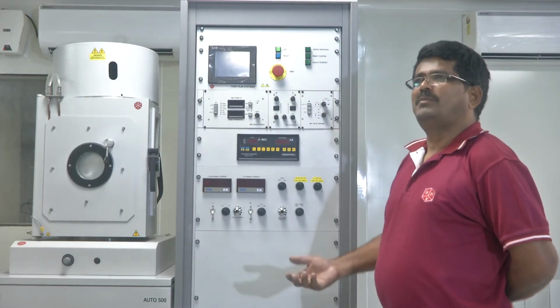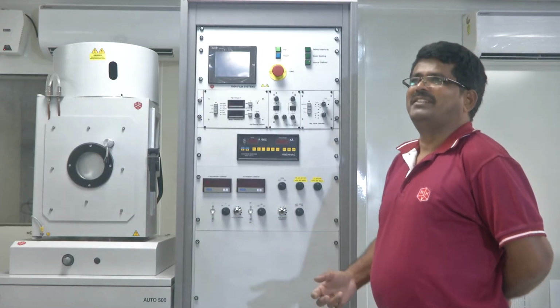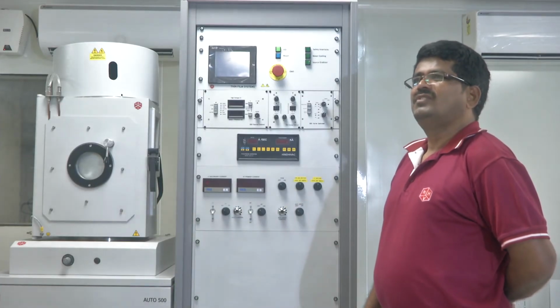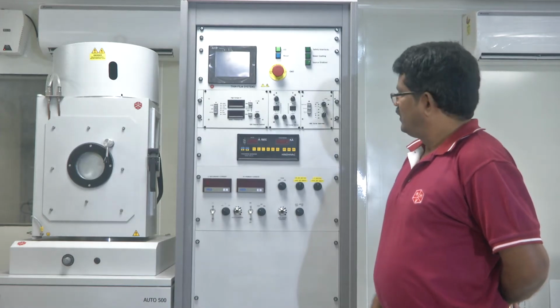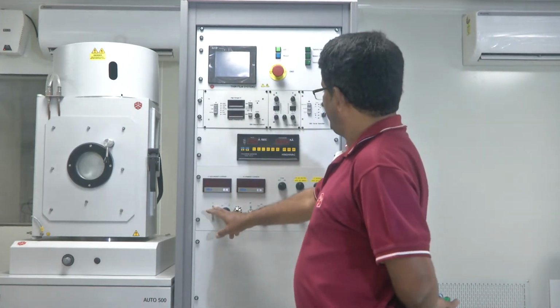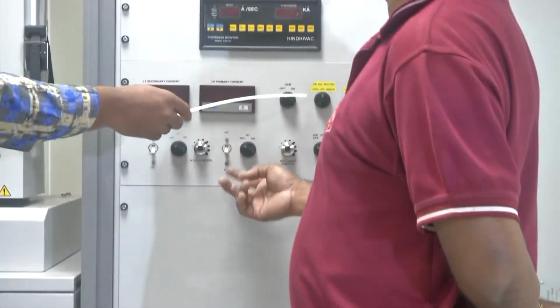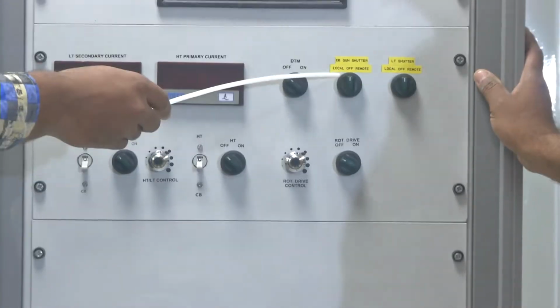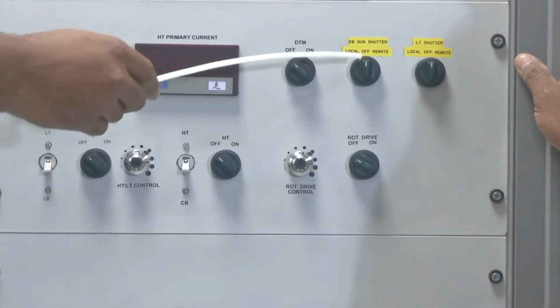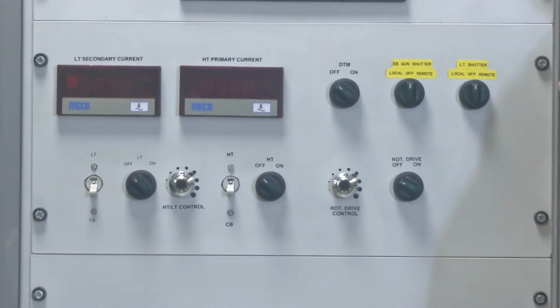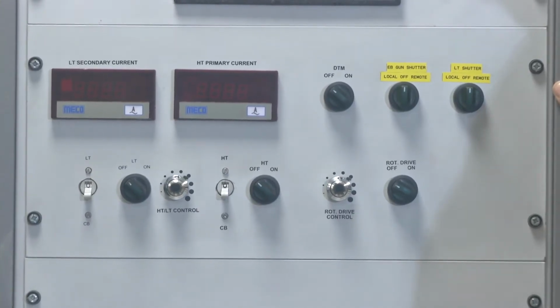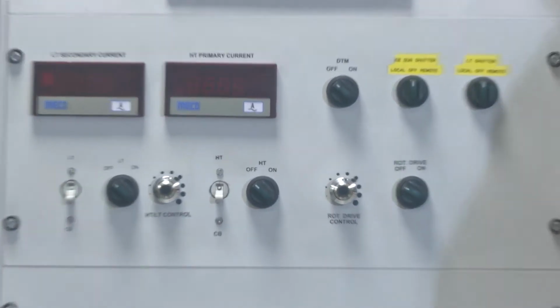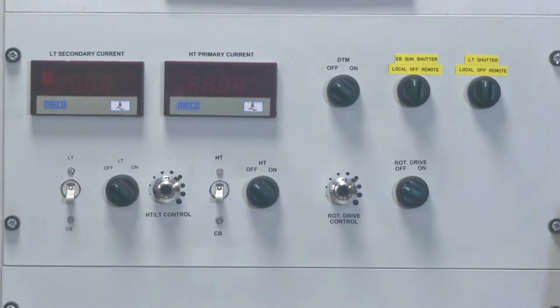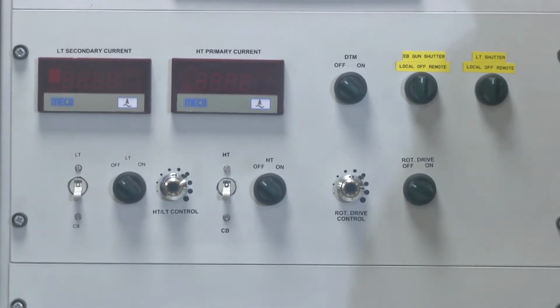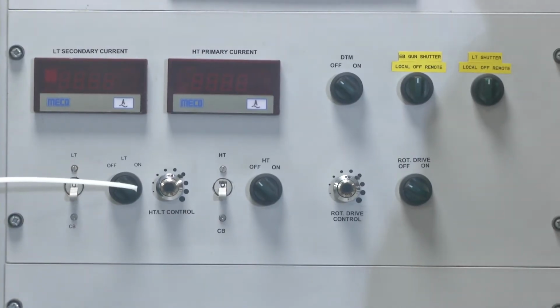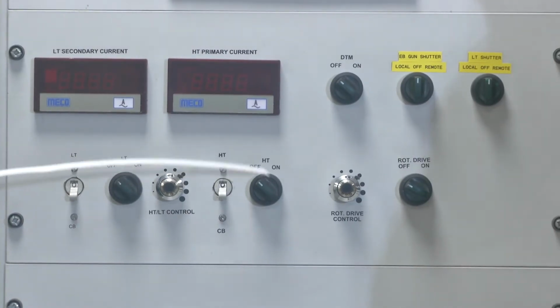The earlier old model just had a butterfly valve, opened and closed manually. So how do we switch between E-beam deposition and thermal evaporation? This is LT, HT. The circuit breaker has local connection and remote connection. If you put local connection, we have to operate manually. If you put remote connection, we go through the HMI. We can do E-beam evaporation and thermal evaporation, but not at a time, only separately. If you want the LT source, we go through this selection. If you want HT, we have to turn on this.